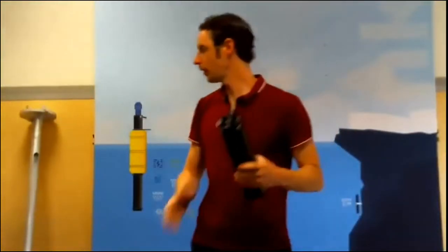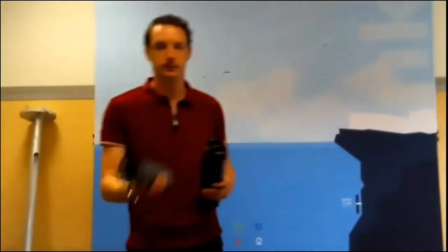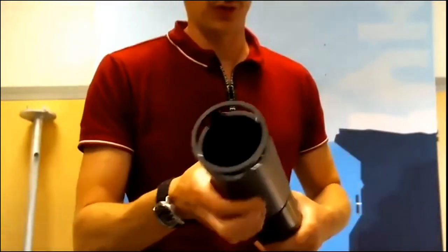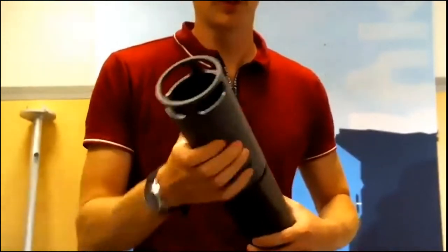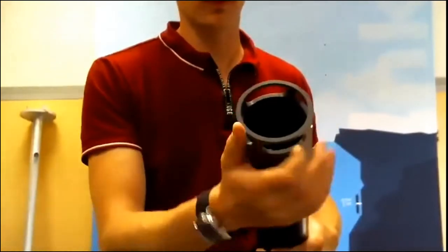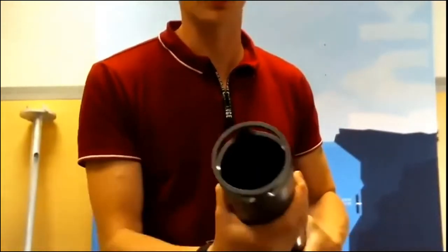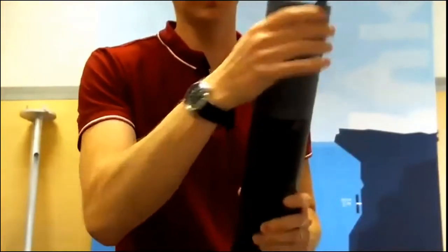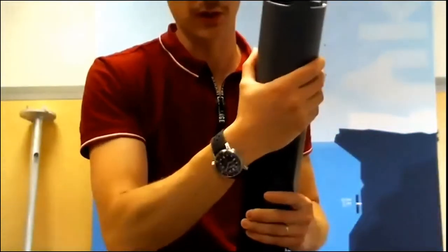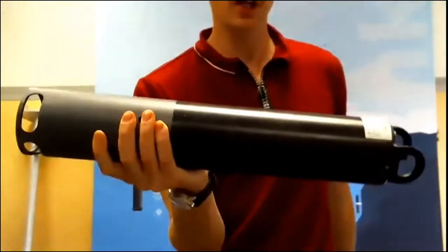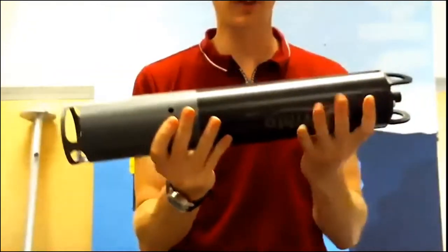Here, you can put the sensor guard that is just screwed on the sonde. The holes that you see on the top are to have the best measurement with the optical sensors, and the holes that you see on the bottom are just to remove the air when we are putting the sensor guard. As you can see, when I have my sensor guard on, I have a fully solid system.